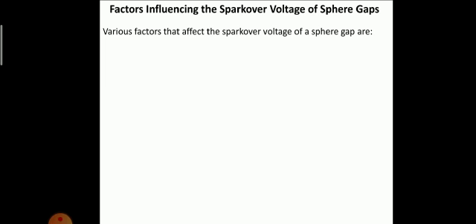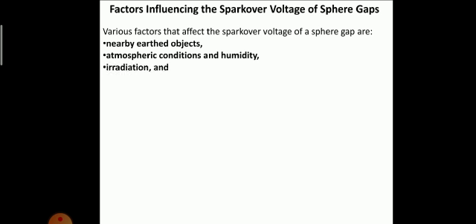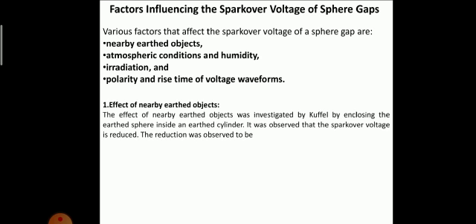This we had already done in module 1, but still we'll brush it up. First, nearby earthed objects will have an effect on the spark over voltage. Second, the atmospheric conditions and humidity. We know what a good conductor is, so moisture content in the air will obviously affect the spark over voltage. Next is irradiation, and the last one is polarity and rise time of the voltage waveforms. Polarity means that if I am applying DC voltage, positive and negative polarity will have effects on the spark over voltage. We'll see them one by one.